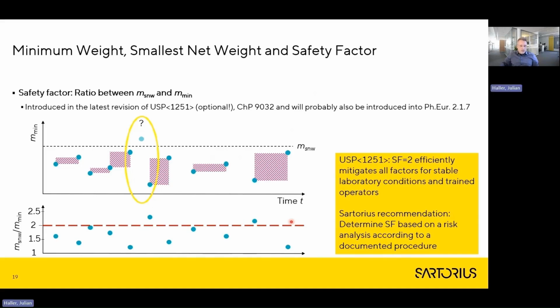The USP Chapter 1251 recommends a safety factor of 2, saying that it efficiently mitigates all factors for stable laboratory conditions and trained operators. We do recommend to determine the safety factor based on risk analysis according to a documented procedure, and we are going to provide a respective guideline and support for users on how to determine the safety factor based on a risk analysis.